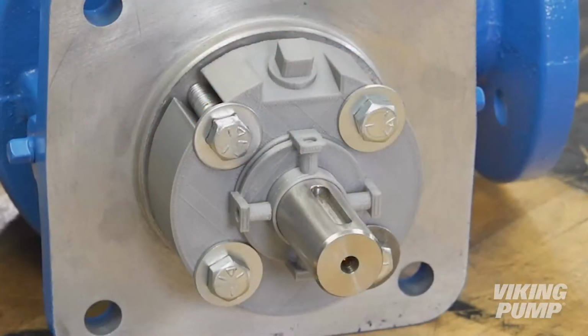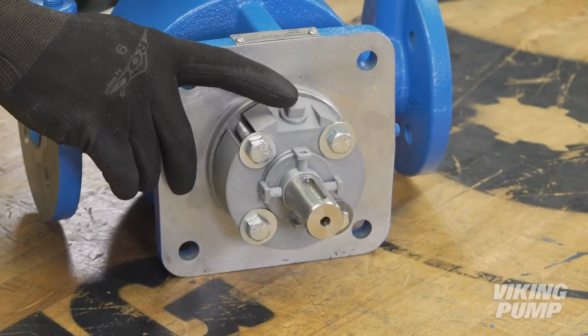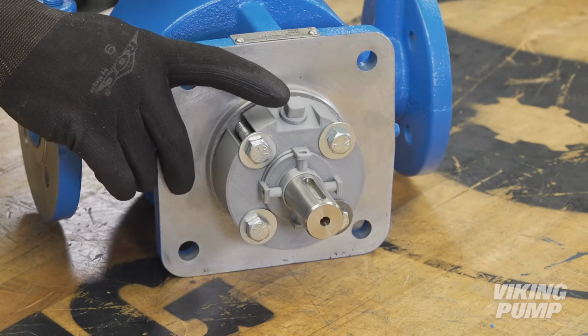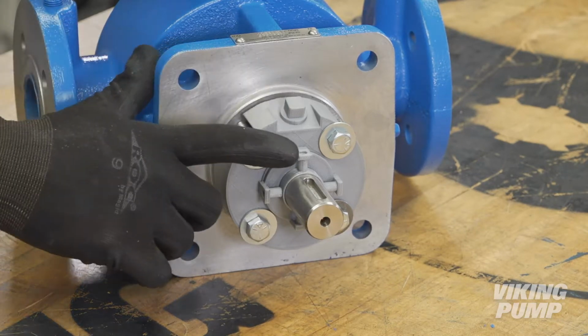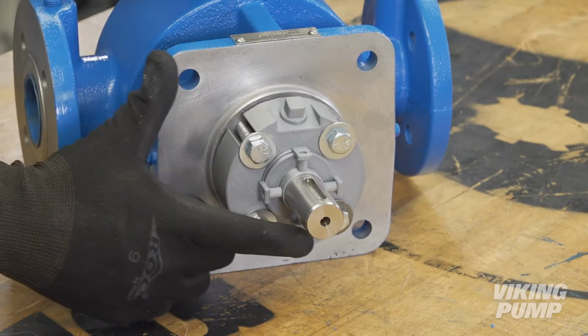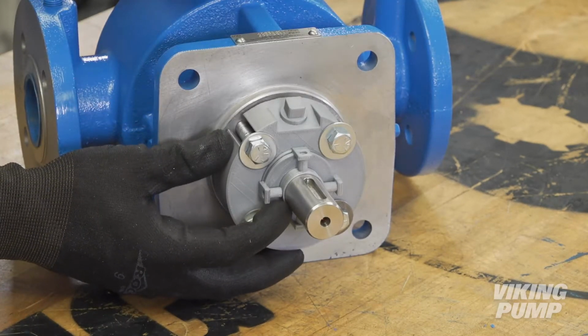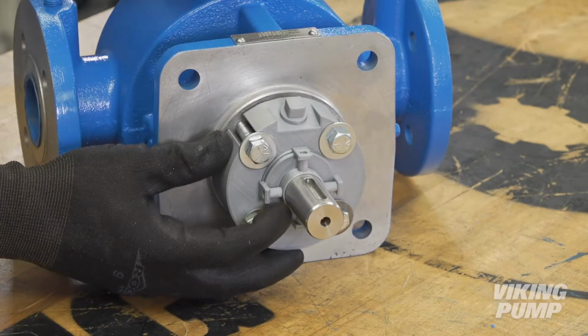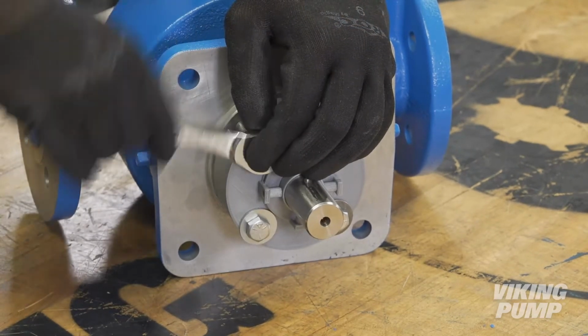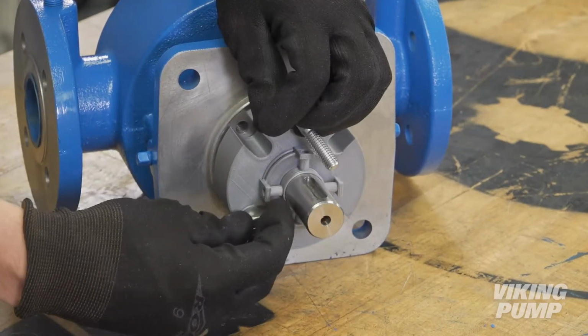For training purposes, a 3D printed mock cartridge seal was used in the making of this video. For removal, first remove any flush plan tubing from the seal gland. Remove the seal spacers. Loosen the seal collar set screws to free the cartridge seal from the shaft. Finally, remove the gland bolts and slide the seal off the end of the shaft.